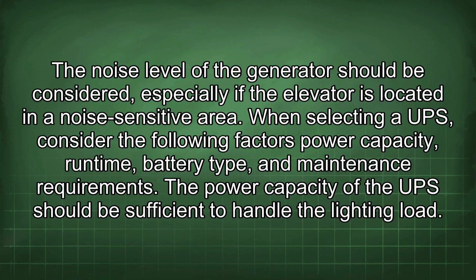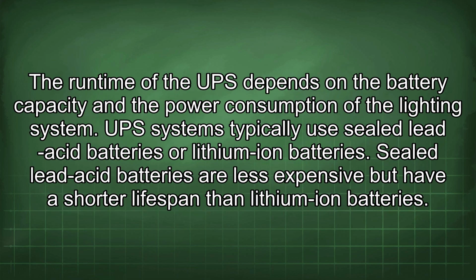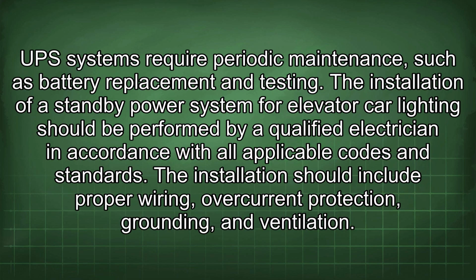When selecting a UPS, consider the following factors: power capacity, runtime, battery type, and maintenance requirements. The power capacity of the UPS should be sufficient to handle the lighting load. The runtime of the UPS depends on the battery capacity and the power consumption of the lighting system. UPS systems typically use sealed lead-acid batteries or lithium-ion batteries. Sealed lead-acid batteries are less expensive but have a shorter lifespan than lithium-ion batteries. UPS systems require periodic maintenance such as battery replacement and testing.